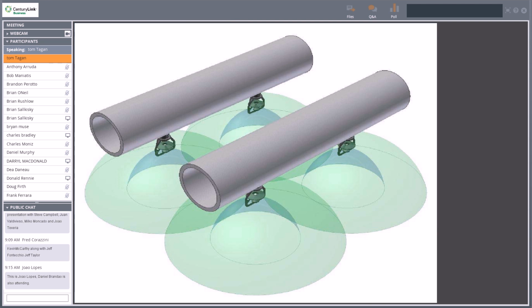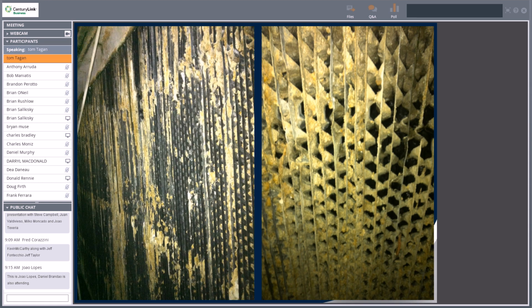Again, this is on the spray. This is what a typical water distribution system would look like out of the spray nozzles. This is the picture I mentioned to you earlier, that you see the scale and growth build up on your fill of a cooling tower. That is causing the efficiency in your system to suffer, and that could very well be from wet-dry operation with an imbalance in your distribution system. If you get wet-dry, scale seems to develop much quicker. So we're trying to keep that scale and that film to a minimum.